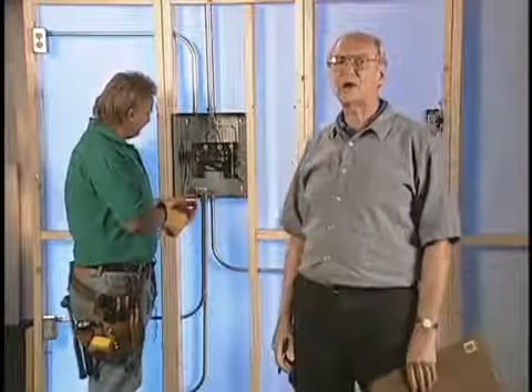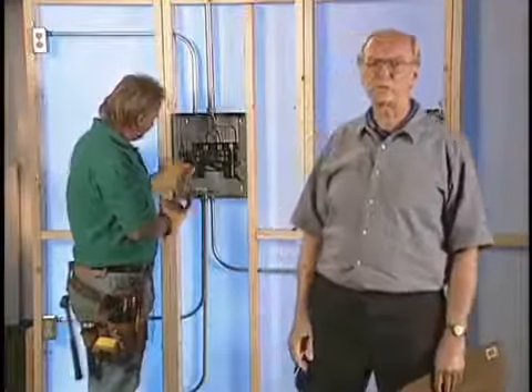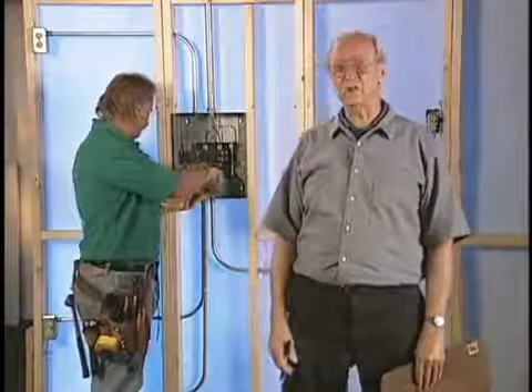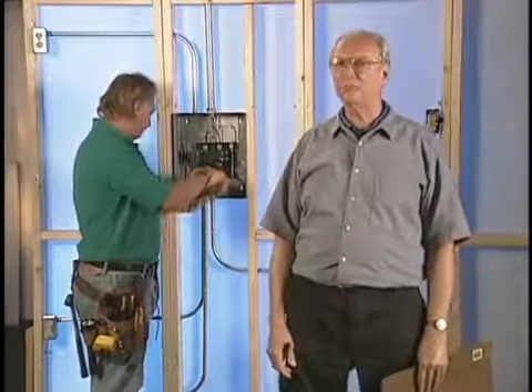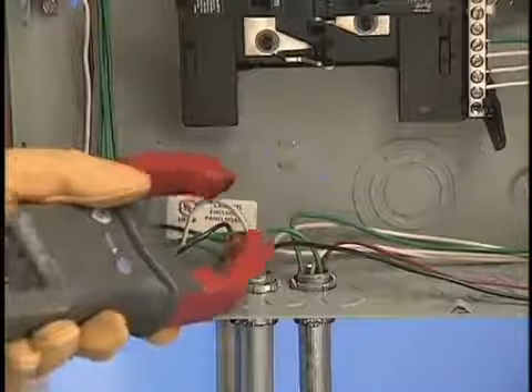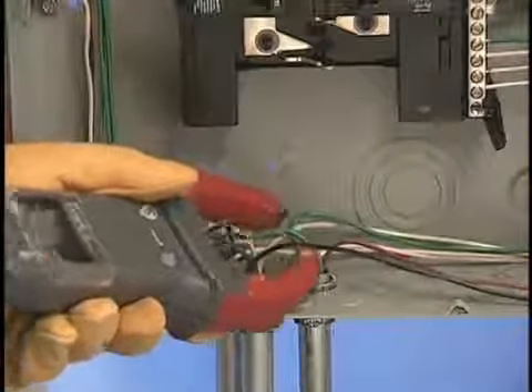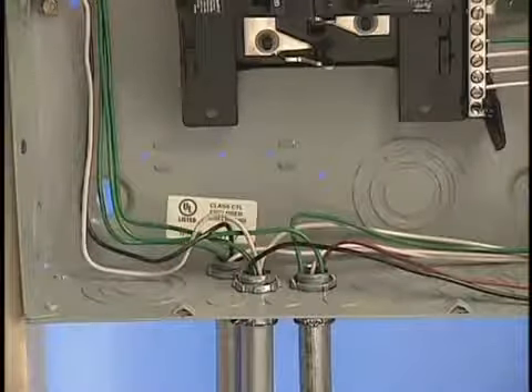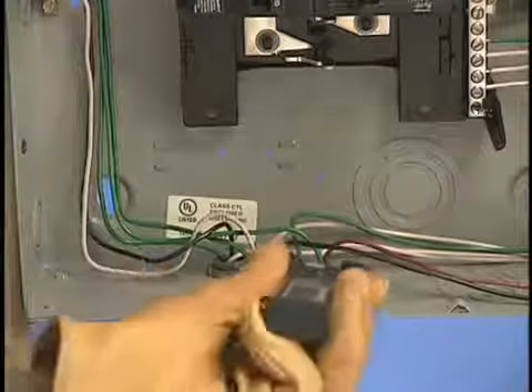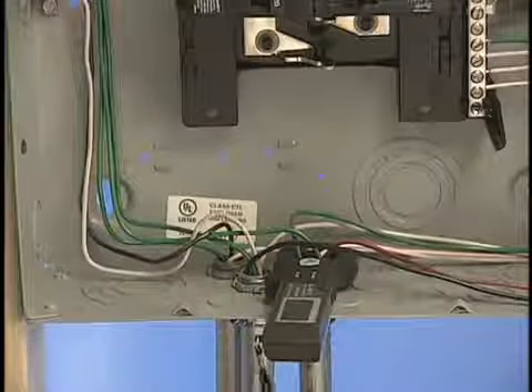The current on the hots should equal the current on the neutral. There should be no current on the ground. If some neutral current is missing, suspect a neutral to ground connection in the panel or in one of the circuits. If there is too much neutral current, suspect a shared neutral with a circuit from another panel.